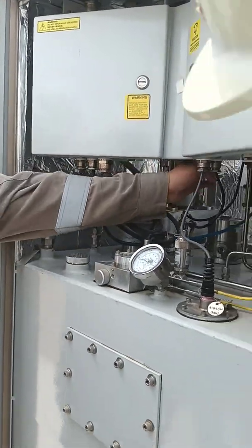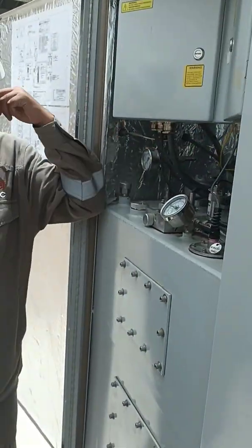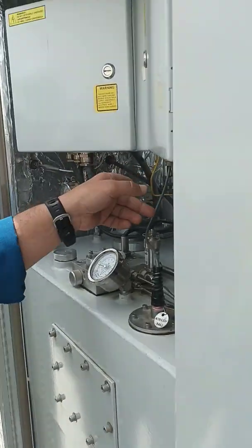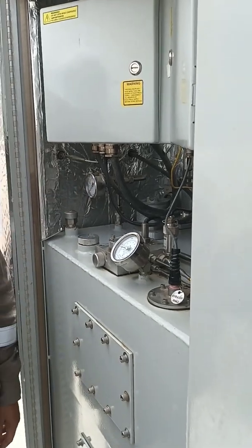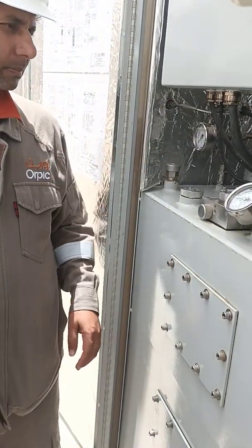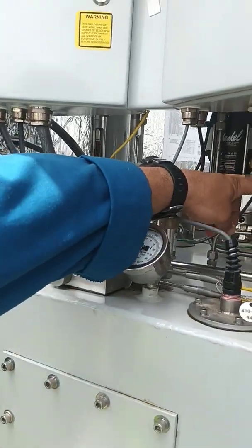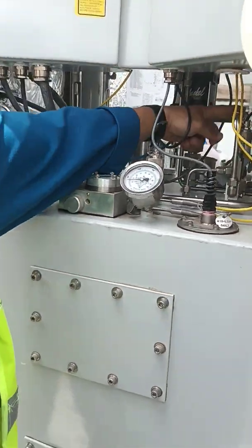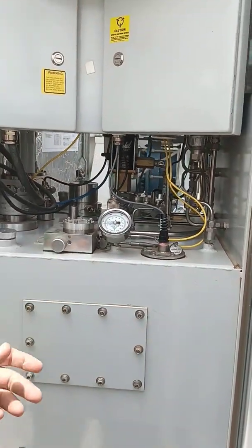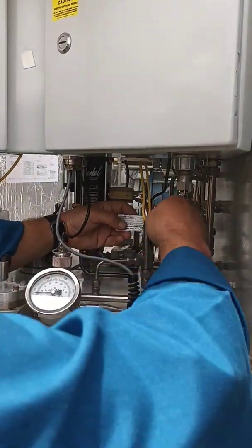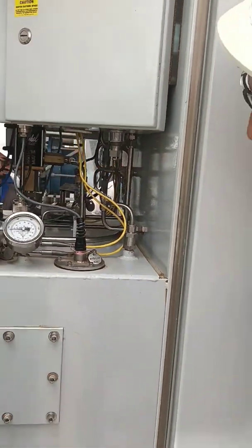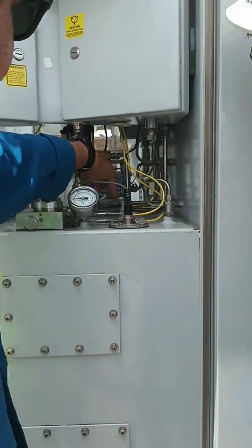Level transmitter. So you have three pressure safety release valves. For the oil mist, you have one each, which is this one, and the one that I opened there, which is the same. If for some reason the mist pressure goes too high, then this one will pop off. And you have the oil supply relief valve, which is this one, which is coming from the pump. The pump is pumping the oil here, and if it's more than, I think it's set to 150 psi, that valve will open and bypass the oil to the tank.